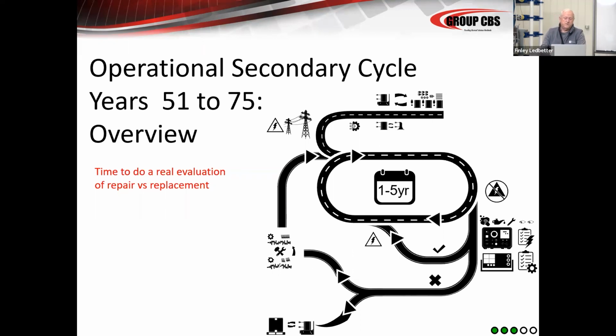Well, most of the people on this call won't be in this business anymore. Most of the people on this call's kids will be in this business, but this equipment will still be in service because there is nothing today to replace it with. And replacing it with like-kind equipment is very feasible in situations where you have plenty of room. You don't mind disturbing the cables and possibly having to replace the cable, or you're willing to put tap boxes in and jumper the cable over, which creates a whole other myriad of problems. So a lot of the gear will just stay in service. So now it's time to do a real evaluation: repair versus replacement.